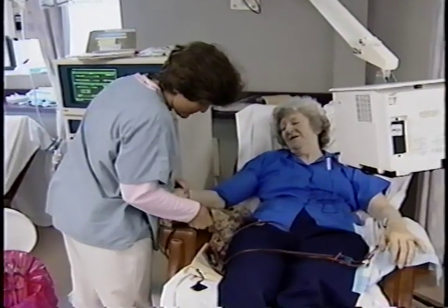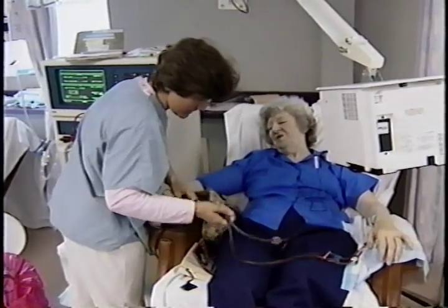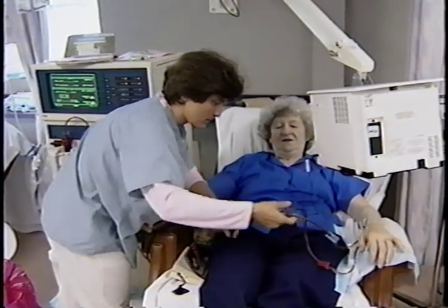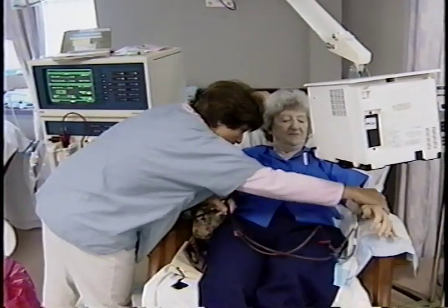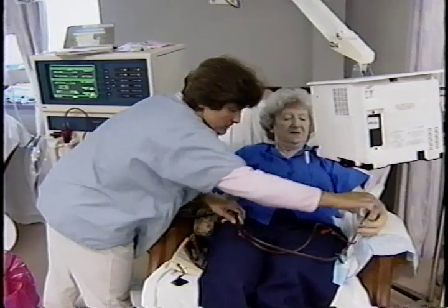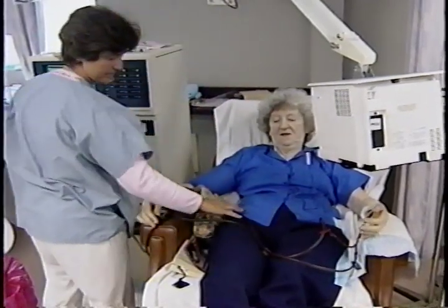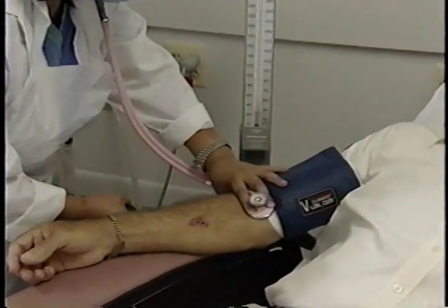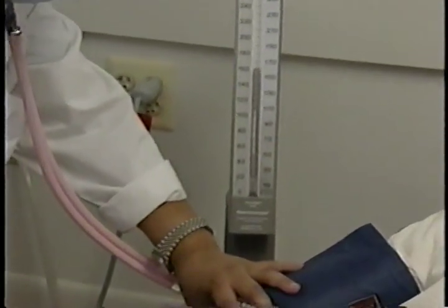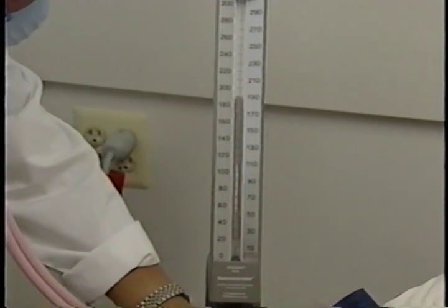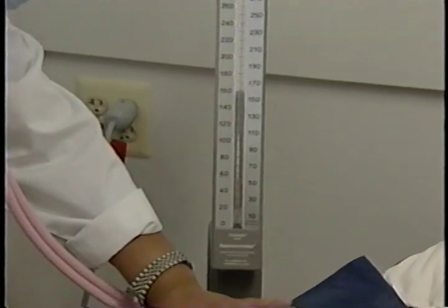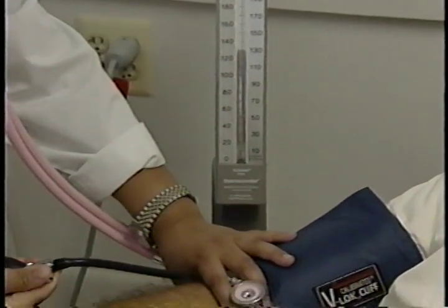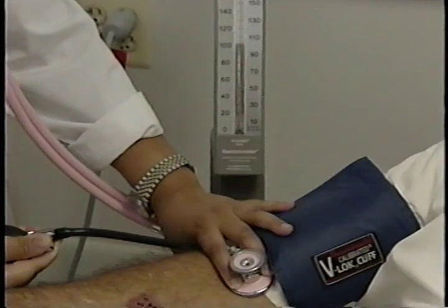Sometimes personal items may obstruct the blood flow, or the patient may have shifted position. At times, even the tubing itself may kink, which could reduce blood flow to a significant degree. Blood pressure should be monitored frequently to assess the patient's condition. A drop in your patient's blood pressure could decrease the flow rate in the access, reducing the blood flow available to the extracorporeal circuit.